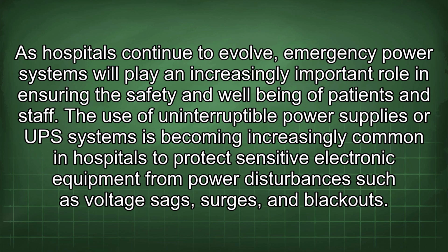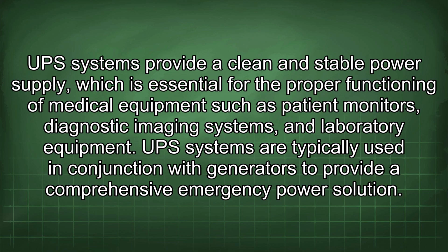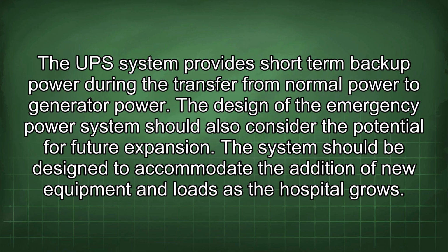of patients and staff. The use of uninterruptible power supplies, or UPS systems, is becoming increasingly common in hospitals to protect sensitive electronic equipment from power disturbances such as voltage sags, surges, and blackouts. UPS systems provide a clean and stable power supply, which is essential for the proper functioning of medical equipment such as patient monitors, diagnostic imaging systems, and laboratory equipment. UPS systems are typically used in conjunction with generators to provide a comprehensive emergency power solution. The UPS system provides short-term backup power during the transfer from normal power to generator power.